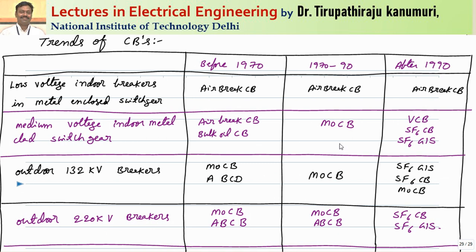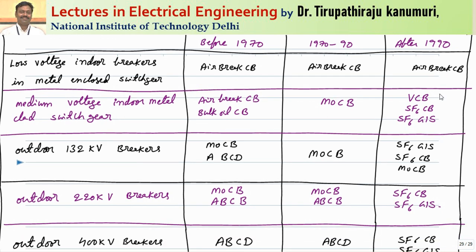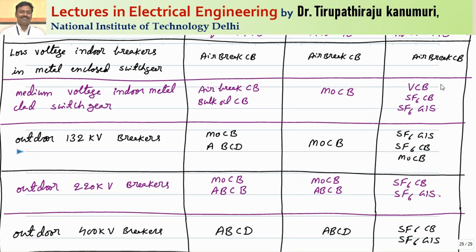What are the current trends? Trends are divided into three phases: before 1970s, between 1970 and 1990, and after 1990. For low voltage indoor metal-enclosed breakers, air brake circuit breakers were used before and are still used today — including the miniature circuit breakers in households. For medium voltage indoor metal clad switchgear, previously air brake or bulk oil circuit breakers were used, then replaced by minimum oil, and nowadays either vacuum circuit breakers, SF6 circuit breakers, or SF6 gas insulated substations are used. The current trend is only vacuum or SF6.